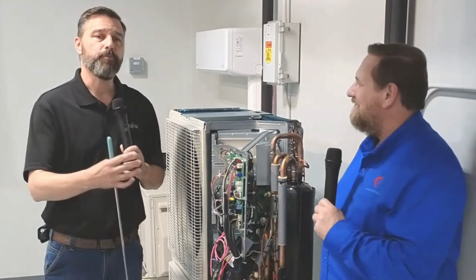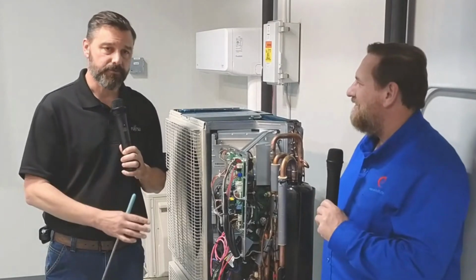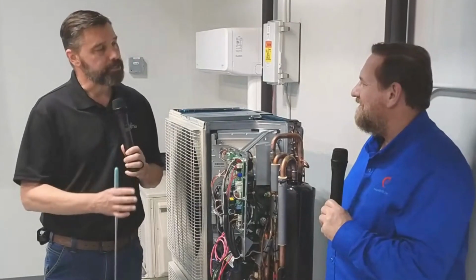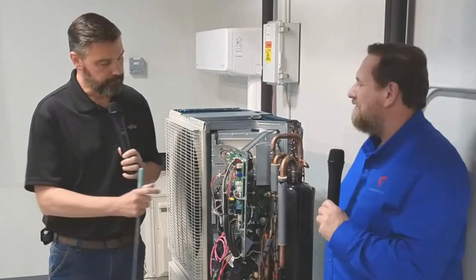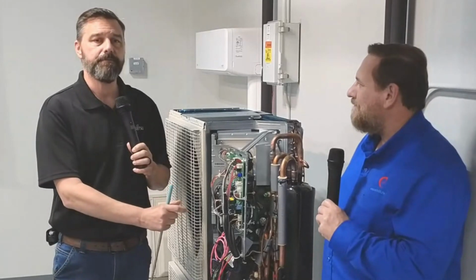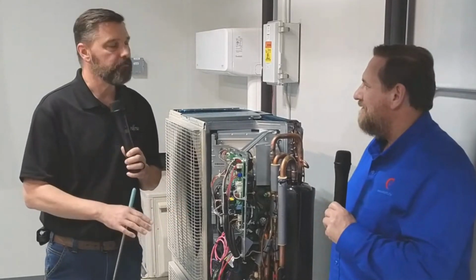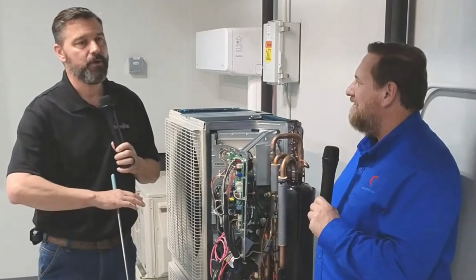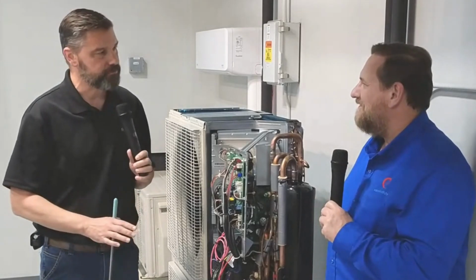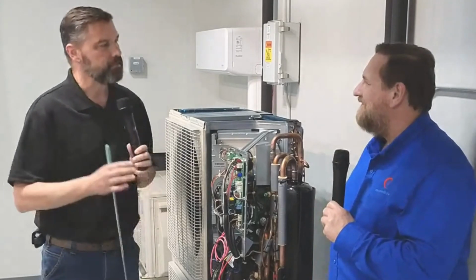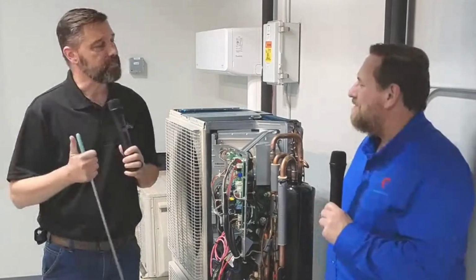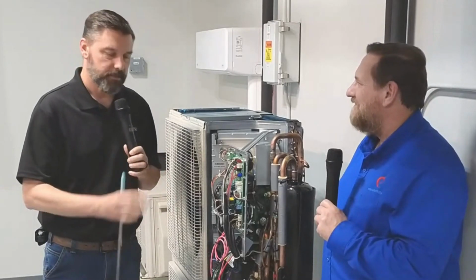After that, we want to pull our vacuum, pull it down to 350 microns, and then watch it for an hour. Isolate your vacuum pump, and make sure your digital micron gauge is on the system. We want to make sure that we stay below 500 microns for an hour so that we know we have a completely dehydrated system that is sealed, tight, and dry. As Juan mentioned earlier, if it's clean, tight, and dry, and you charge it properly, this system's going to run.